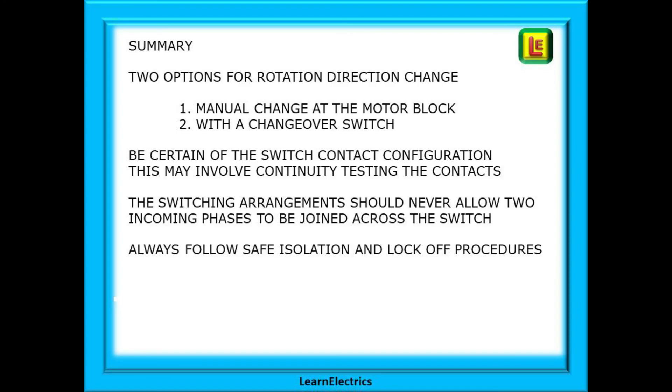So we have two options for changing the direction of rotation: a manual change at the motor block or with a changeover switch. Be certain of the switch contact configuration. This may involve continuity testing the contacts, but it is better to be safe than sorry. Check twice, switch on once. The switching arrangements should never allow two incoming phases to be joined across the switch. And always follow safe isolation and lock-off procedures on any circuits that you work on.